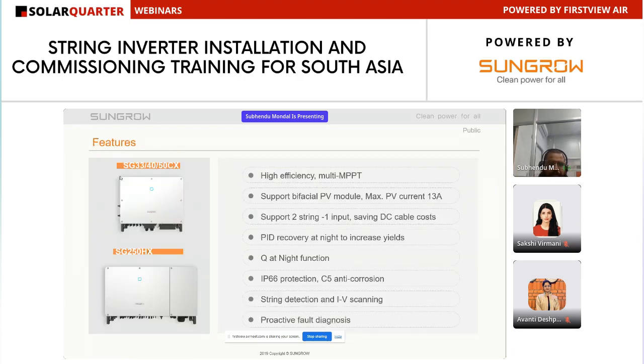So let's move to the features of our inverter. First is high efficiency. Our inverter has more than 90% high efficiency. Also, it has multi-MPPT benefit. By using the multi-MPPT benefit, we have less chance of string mismatch. Next, our inverter supports two strings to one input, saving DC cable cost. We will discuss this on upcoming slides also. Our inverter supports PID recovery at night to increase the energy yield. So as you know, PID recovery is a very important part.